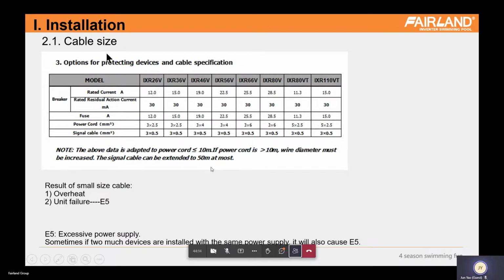The next one is cable size. For every unit, we have the cable size recommendation in our instruction manual here, including the power cord and the breaker, the fuse for every unit. We need the installer to do it according to our recommendation based on the standard. The sizes are based on 10 meters. So if it is more than 10 meters, you need to use a bigger wire size.